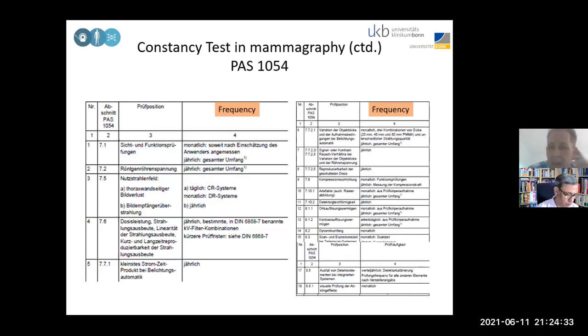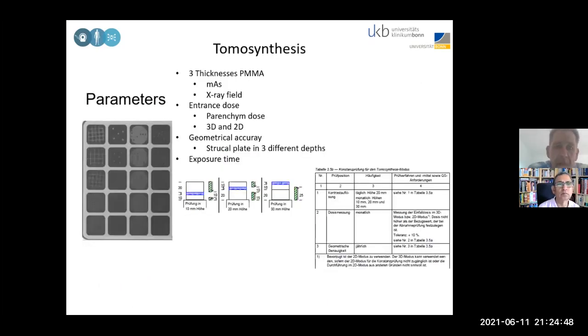So again, there is a PAS 1054, that is again a German one. There is written down the frequency, how to check for contrast, geometry, dose, and time needs to be done. For example, we do the contrast for several thicknesses. Of course, the breast could have several different thicknesses. So there are three standard sizes of breast thickness: 20, 40, and 60 millimeters. Then you check there the mAs with a certain kV. Usually you use a rhodium source, and the kV is adapted to the thickness. You start with 26, 28, and then 30 kV for the thickest field.